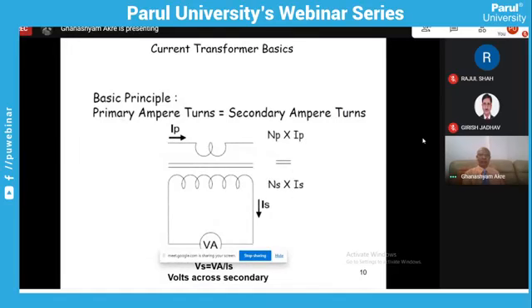We'll come to the principle of operation. You can see here a popular schematic winding drawing. Here the primary is shown as IP, secondary is shown as IS. It is connected with VA burden. In a current transformer, the load is actually called its burden, unlike power transformers and distribution transformers, where it is load in kVA, MVA. So here the load is very low. So it is called a burden.